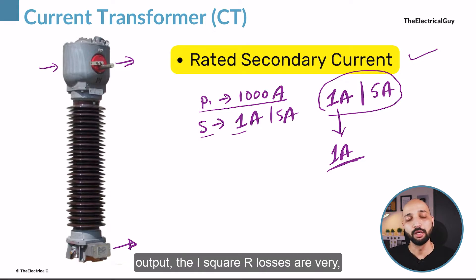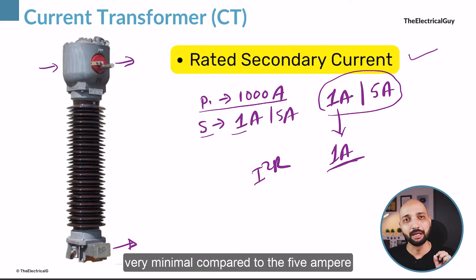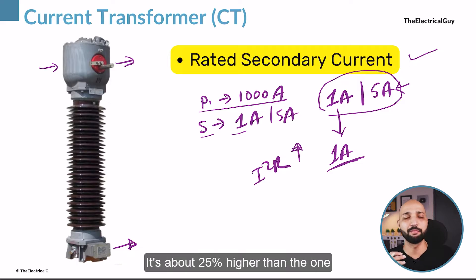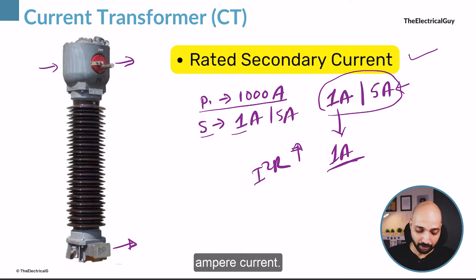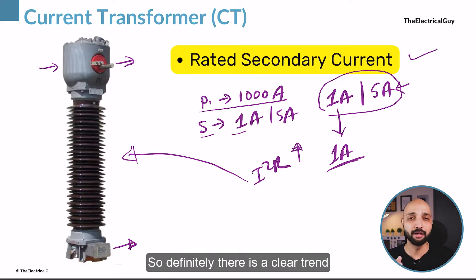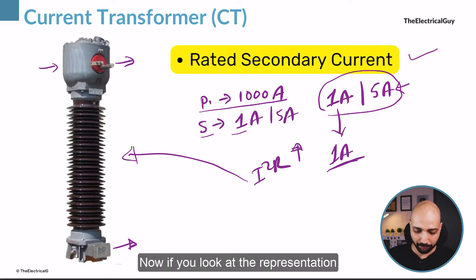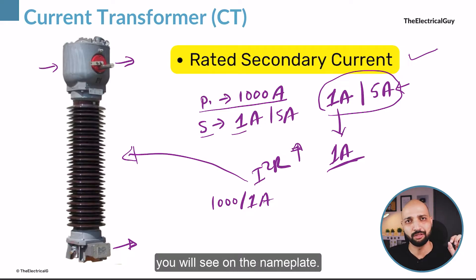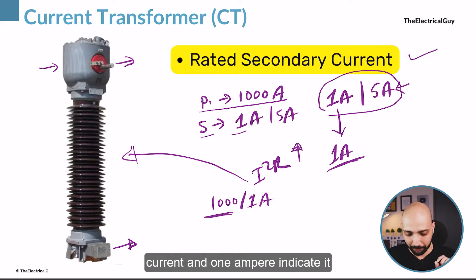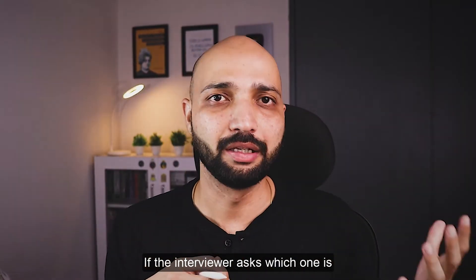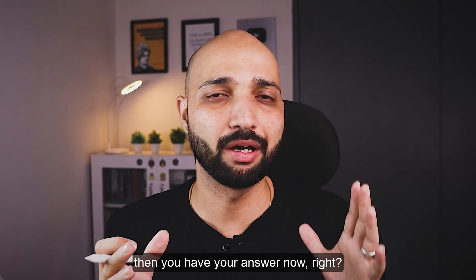There is a clear trend towards 1 ampere secondary current. When you use 1 ampere as a secondary output, the I²R losses are very minimal compared to 5 ampere. With 5 ampere, the I²R losses are about 25 times higher — that additional burden on the CT makes it heavier and more costly. The nameplate representation is generally shown as 1000/1 A, where 1000 indicates the primary current and 1 ampere indicates the secondary current.